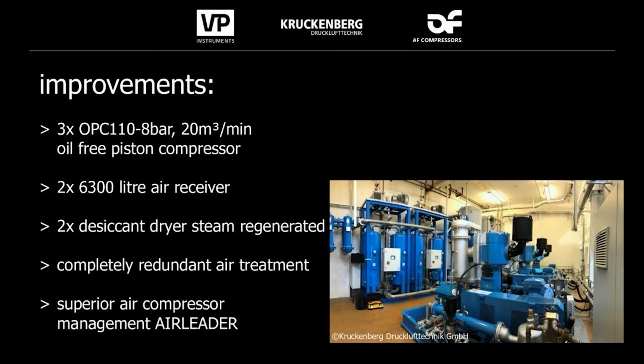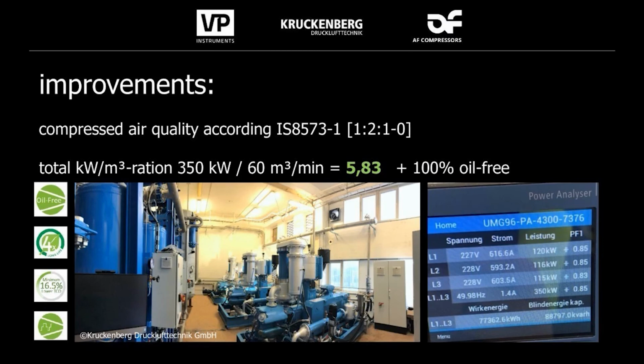And on top, a superior compressed air management system to visualize and to collect all of your KPIs. We have flow measurement for the individual compressors, individual kilowatt measurements for each compressor, and a complete kilowatt measurement for the complete installation, for the complete air compressor room, plus a reactive energy measurement for the complete installation. And this is leading us, and these are real measured figures, to a cubic meter kilowatt ratio of 5.83 compressed air for the complete compressed air, full power, with minus 40 degrees. 100% oil-free, which is a very good value. Nobody was expecting this in the beginning.